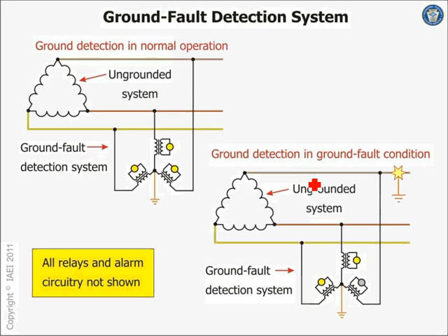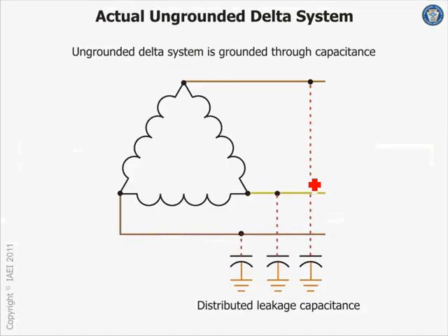So you can go as low as just a lamp went off, there's a ground fault, go fix it, search for it basically in this huge plant. Or it could go as far as telling you how much current and sensing where that ground fault is sitting on your system, which panel. So that's your ungrounded system.